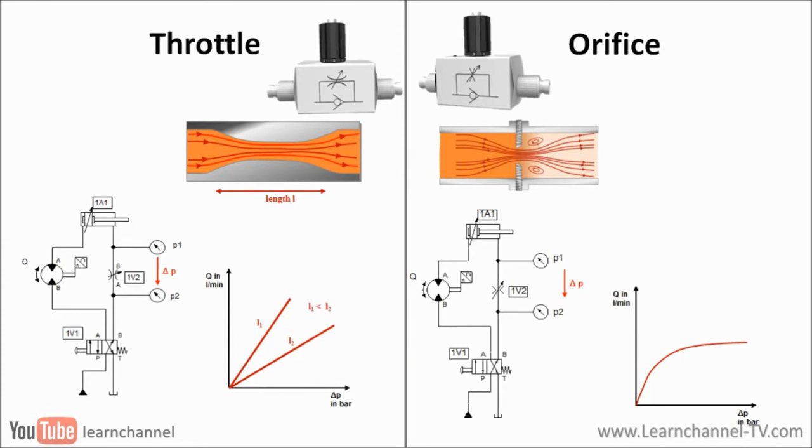Regarding the orifice, the viscous fluid friction is very low and thus the flow rate hardly depends on the viscosity of the oil. This is an advantage. On the other hand, you see a big amount of swirls especially at the exit point of the orifice.